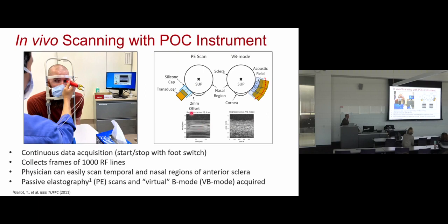And in the bottom scan, we do the opposite. We want to stay at the same position because we want to track these tiny shear waves, elastic waves, to estimate the stiffness. So we ask the clinician to stay as static as they can, and actually, surgeons are very, very good with their hands. I couldn't do this, even though it's a fraction of a second. You cannot see it here. We also had to decide how to do the measurements; it was not clear. Here he has a piece of foam where he puts his elbow, and so he's very stable with the patient in the eye. So if you're asking exactly which portion of the eye we measured, well, the ophthalmologists know where it's going, but then we're talking about 10 micron resolution, so of course it's not consistent exactly from eye to eye, but there's no co-registration step. Did I answer your question?